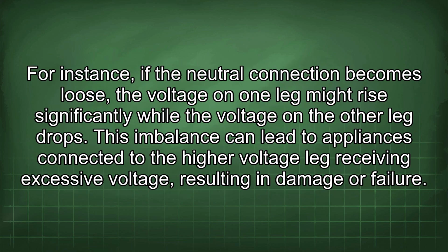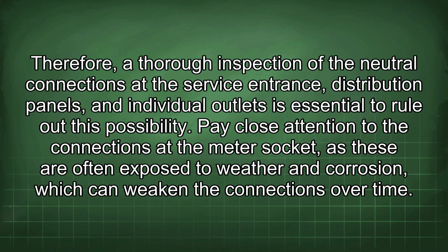For instance, if the neutral connection becomes loose, the voltage on one leg might rise significantly while the voltage on the other leg drops. This imbalance can lead to appliances connected to the higher voltage leg receiving excessive voltage, resulting in damage or failure. Therefore, a thorough inspection of the neutral connections at the service entrance, distribution panels, and individual outlets is essential to rule out this possibility.